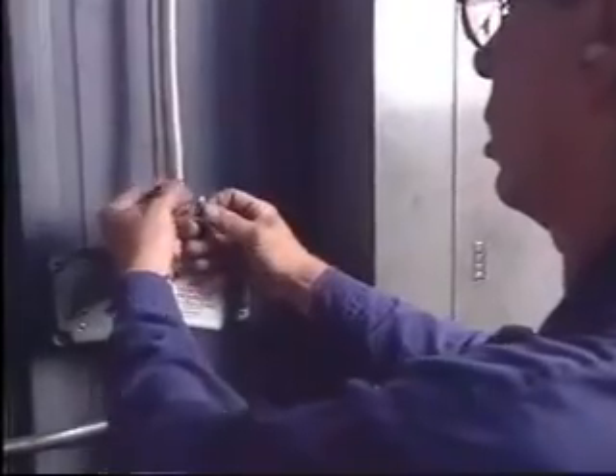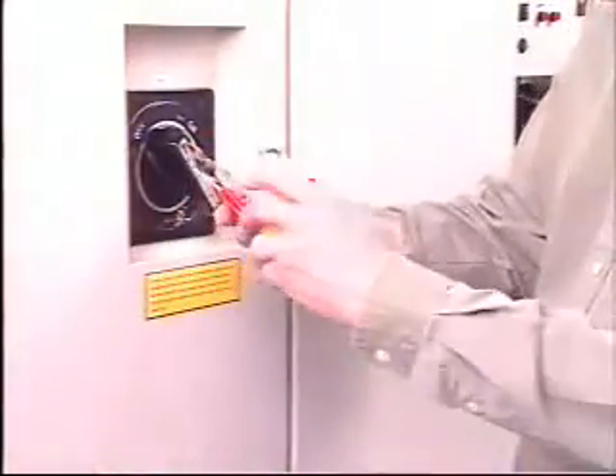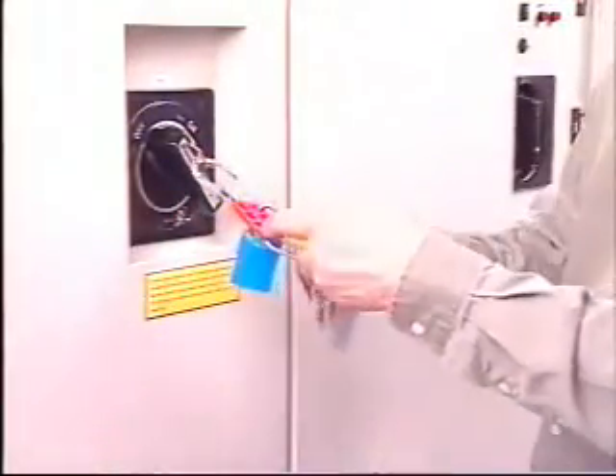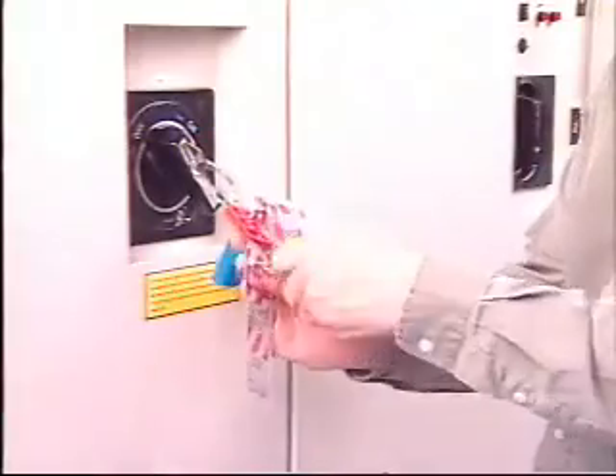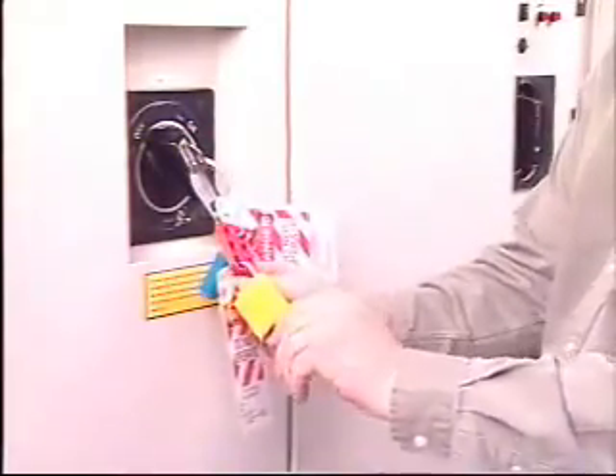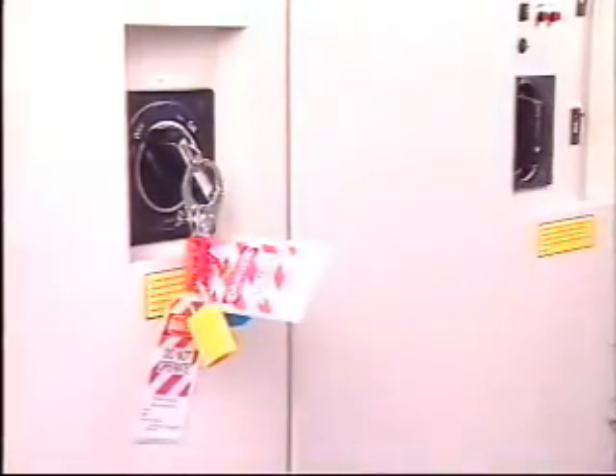If it's not possible to lock out an energy source, a tag alone can be used as a warning device. Treat this tag as if it is a lock. If several people are going to work on a piece of equipment, each one must apply his or her own lock. In this case, you'll need a multiple lockout device.